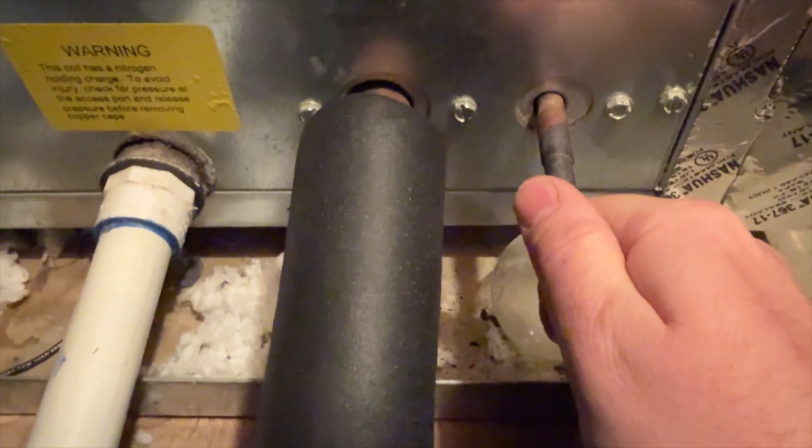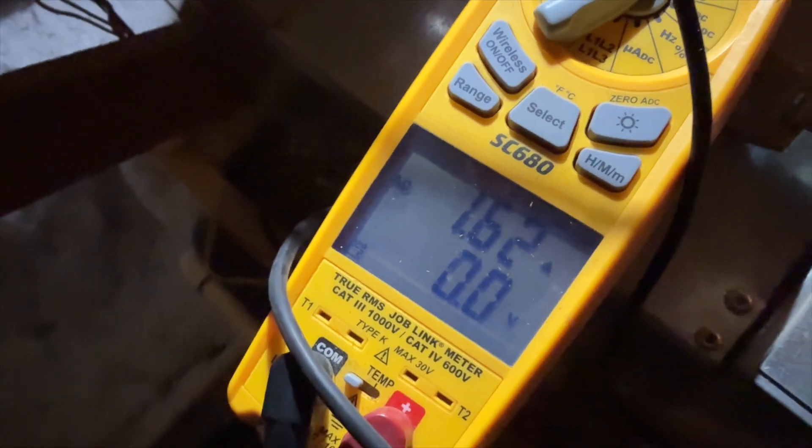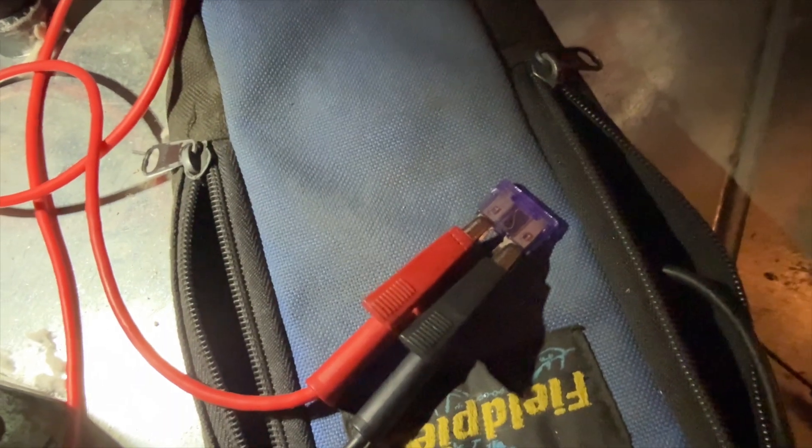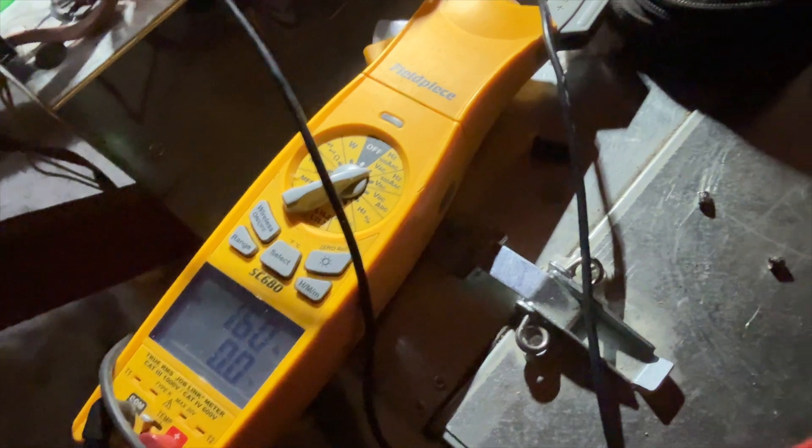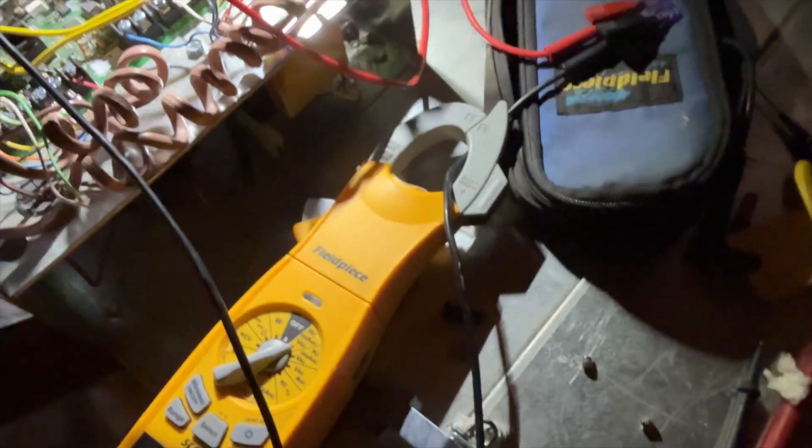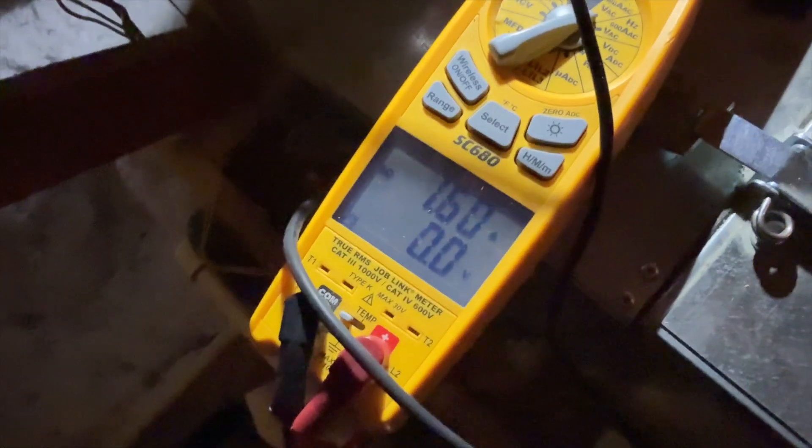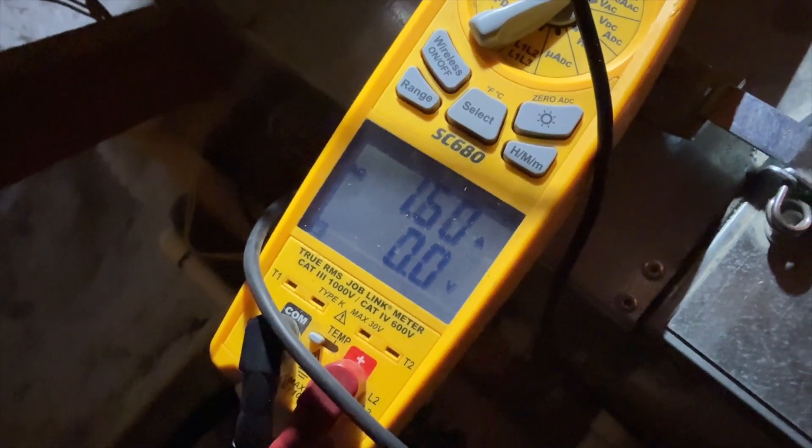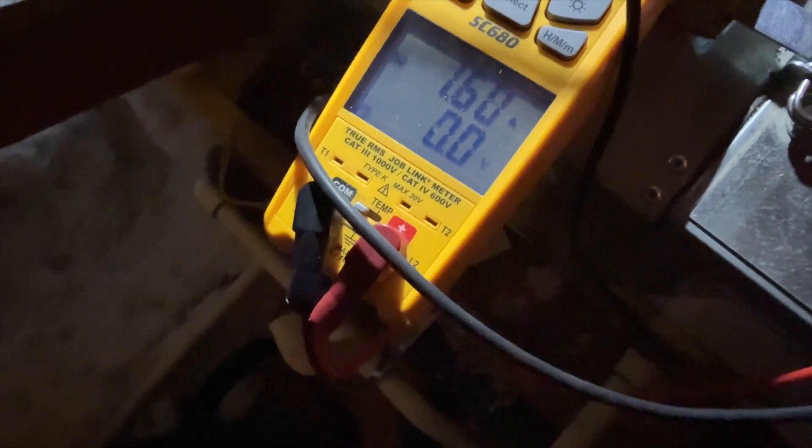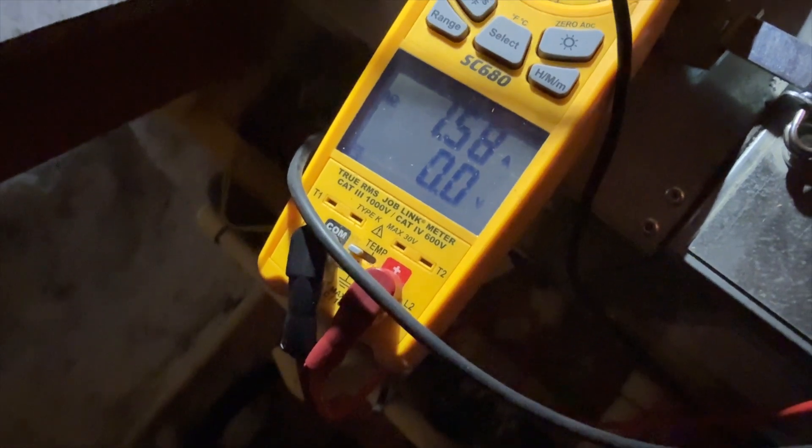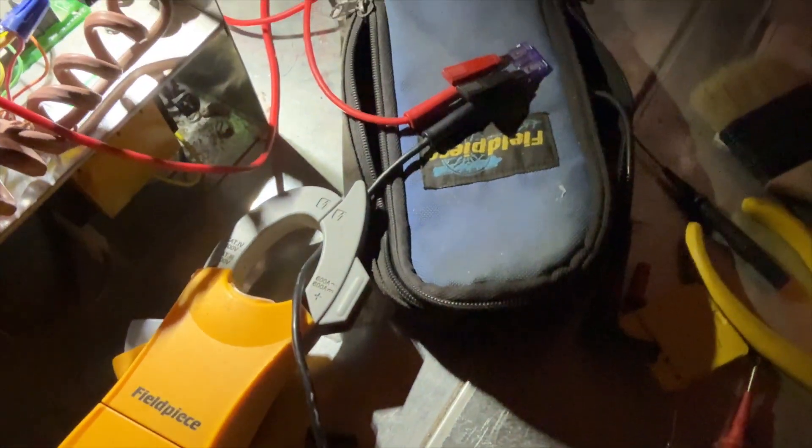All right, heat pump is energized. All right, we're using 1.6 amps. That's looking all right. It's not glowing or anything, so the heat strips haven't energized. So I think we're good. I'm definitely gonna put a 3 amp fuse in this thing. I think two and a half is probably a little too small for this.